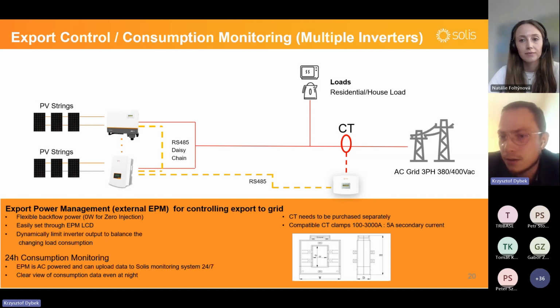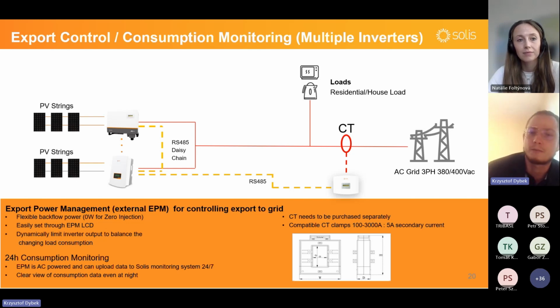But how do you know which CT size is correct? So you should check what is the real maximum current at this site. The best place you can check is go to the main circuit breaker and see if it's written, for example, 120 amps. Then you know that you need CT slightly higher than this. Let's say 150 to 5. So if you have commercial and utilities site, the best way is to check directly on your transformer and add to it, let's say 25% more.